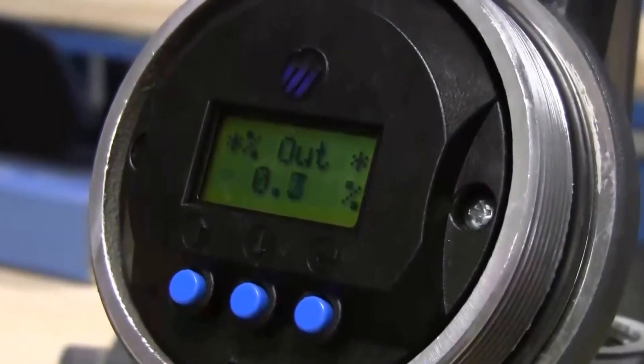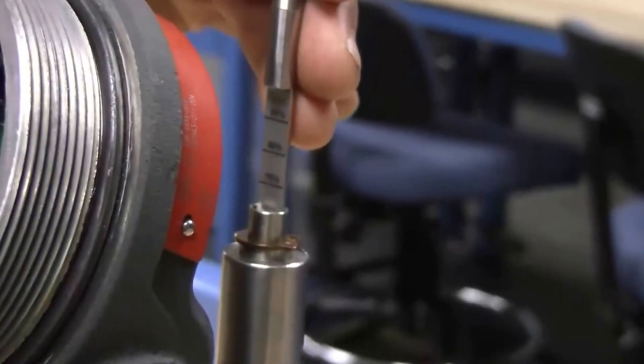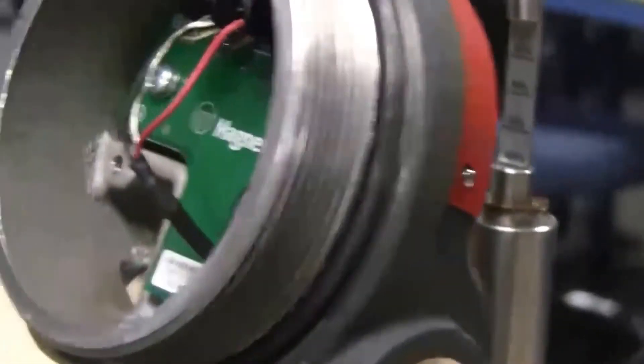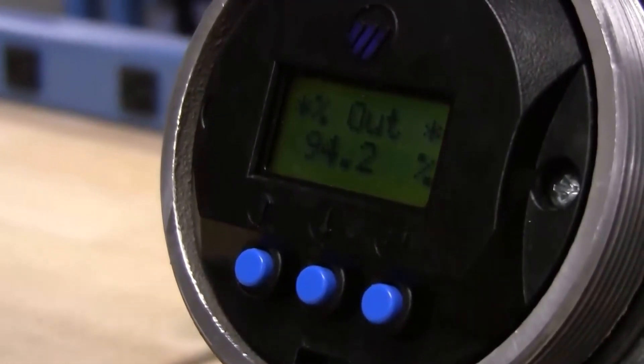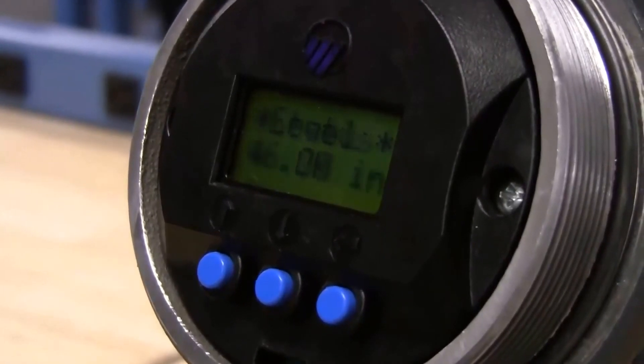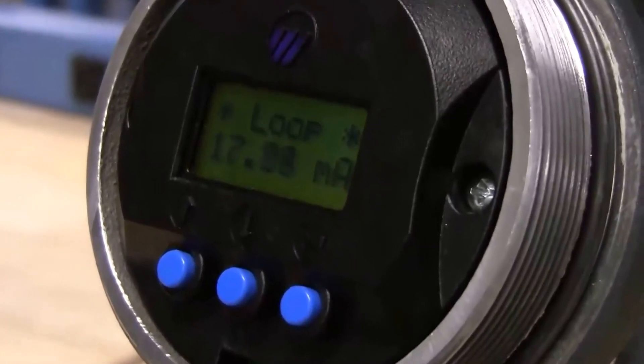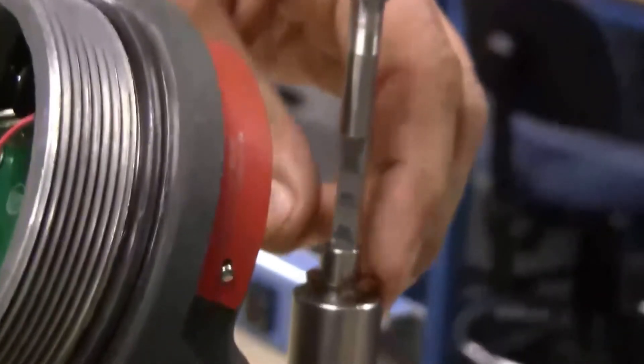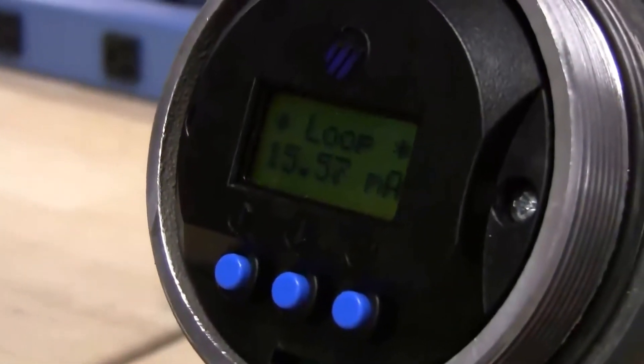You can raise it up to 100 percent. That's pretty close to 100 there. And you'll see we'll be at 20 milliamps or so, closer to 48 inches. Off a little bit there. Let me bring it up a little bit. And if I drop it down to 75, we'll see 36 inches and 16 milliamps, about 75 percent.